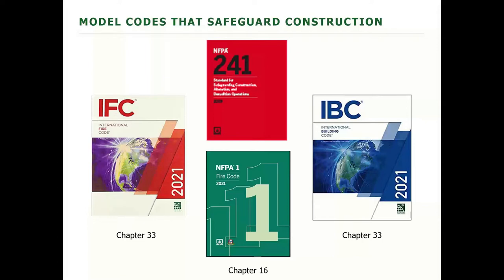Chapter 33 of the IFC deals with construction site fire safety. NFPA 1, Chapter 16, deals with construction site fire safety. Chapter 33 of the IBC deals with construction site safety, but doesn't really have a whole lot in there about fire safety—it references the IFC. But the grandfather of all of these when it comes to construction fire safety is NFPA 241, which is a standard.